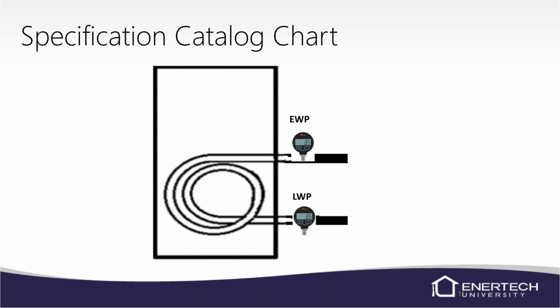If ever you check your entering water pressure and it's lower than your leaving water pressure, then your flow is going backwards. Or for some reason the unit is mislabeled. That has happened a few times, but normally you've got the flow reversed. It's not the end of the world, but we don't get good turbulent flow if we run it through there backwards. So you'll notice a little bit of performance drop if you were to run it backwards.